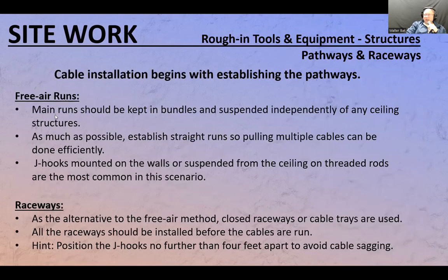All right. So here, main run should be kept in bundles and suspended. Here is the other part of the sentence. Independently of any ceiling structures. That mostly applies to the data because if we go to electrical wires, you're going to have those independently supported anyways. Right?